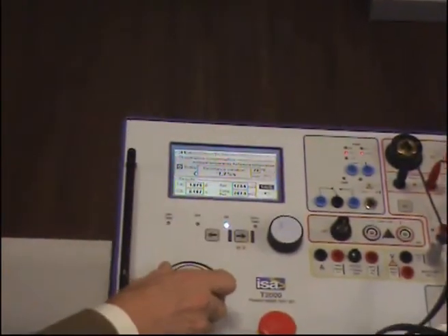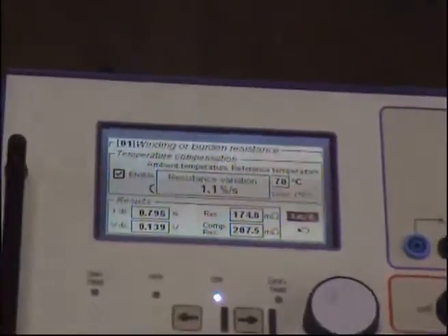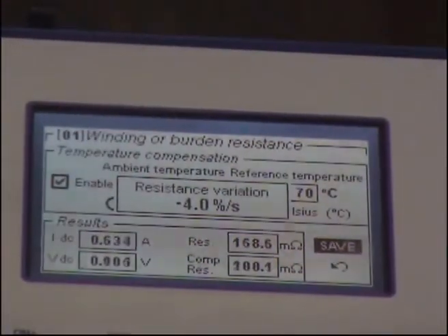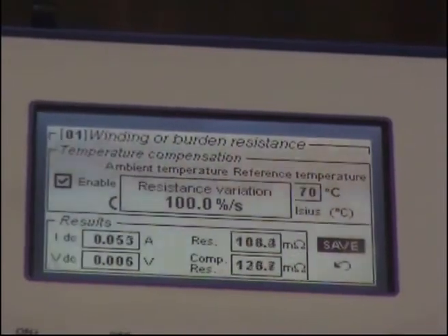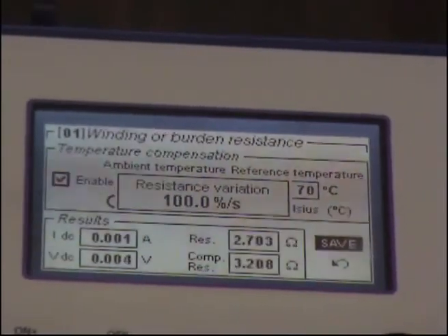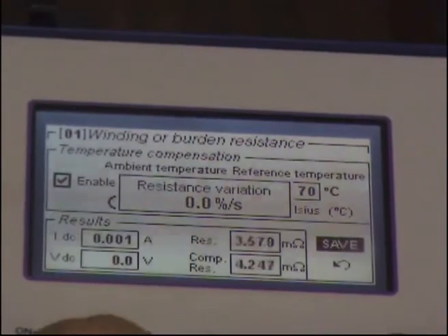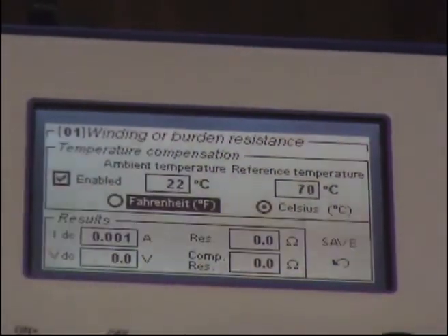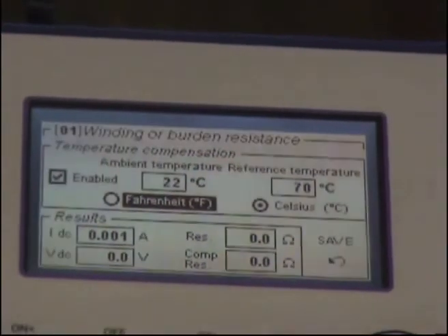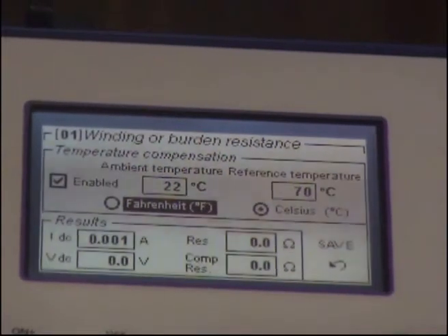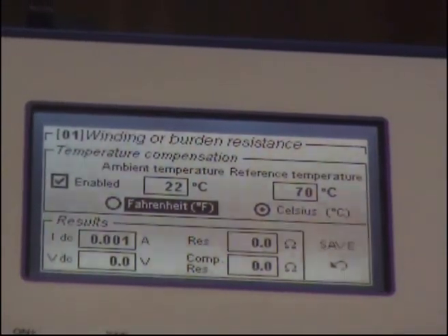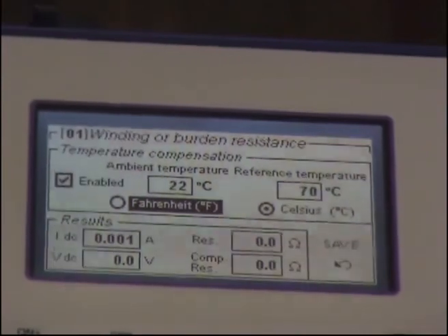go down very slowly. And as you do, you see, it takes some time before the resistance measurement is correct. Okay? And that's it. Last, I repeat, after this test, please go to a curve saturation test, apply AC voltage and reduce it slowly so that the remanence is removed.